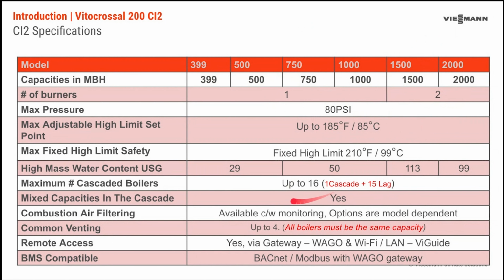The CI2 is cascadable, and it's cascadable with no additional cascade controller. So up to 16 boilers, with one boiler being the lead and the remaining boilers being the lag. We can mix capacities in a cascade. We can mix BTU inputs. An optional combustion air filtering system is available. And in terms of cascading, we can also common vent boilers. We can actually common vent up to 4, with the caveat that all of the commonly vented boilers are of the same BTU capacity.